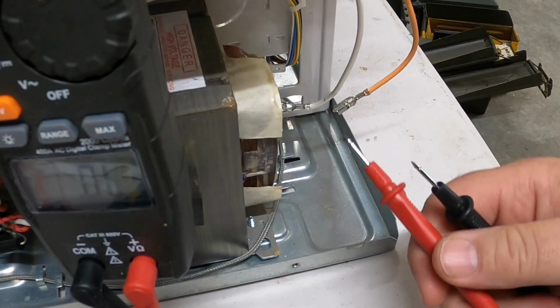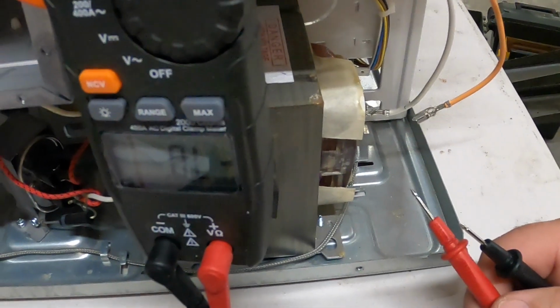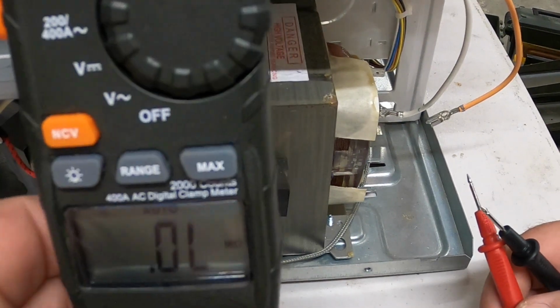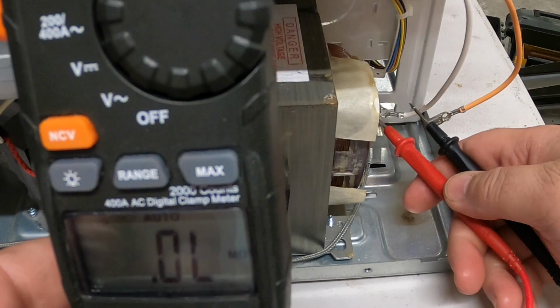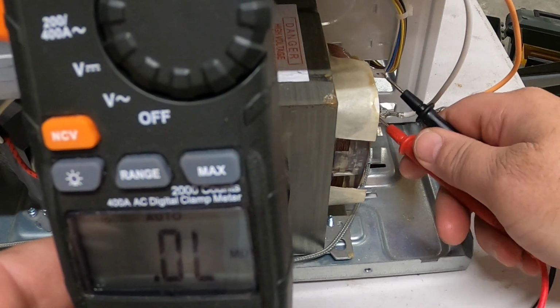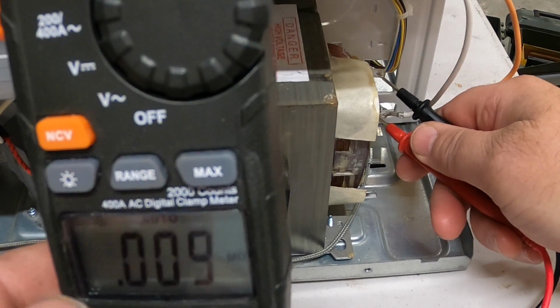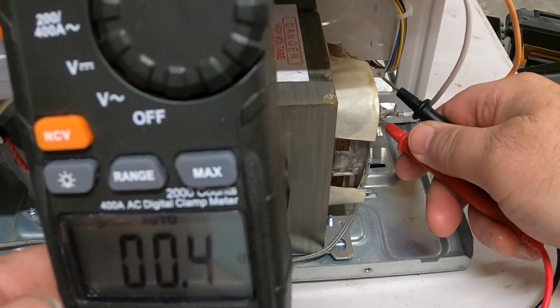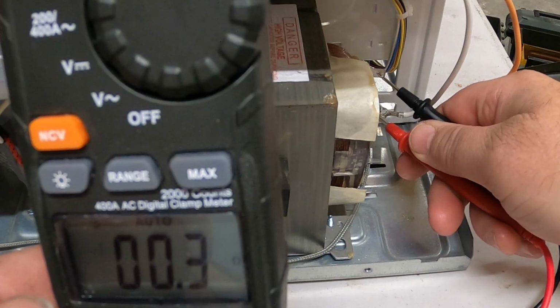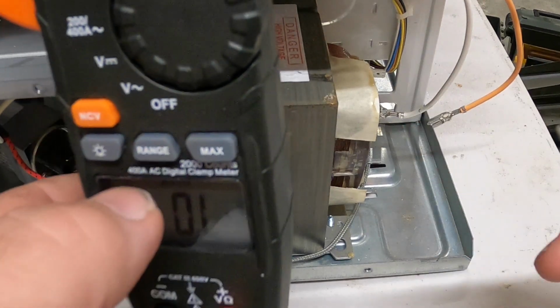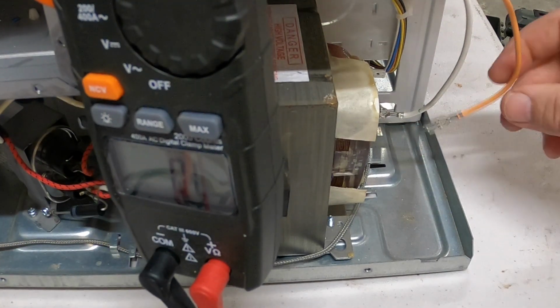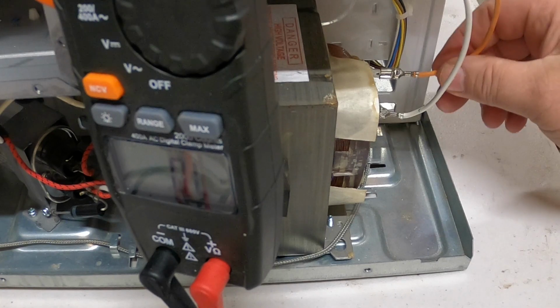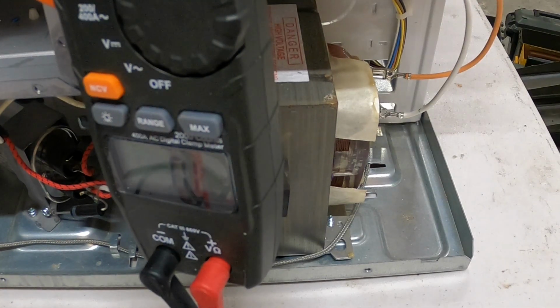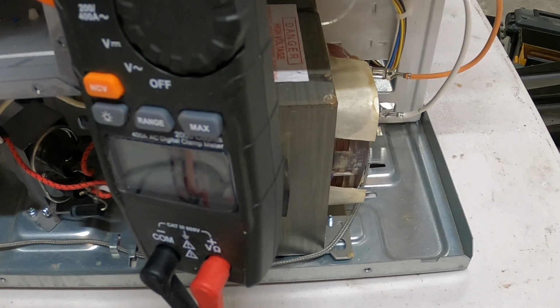You come in here, try to get the meter in. Okay, you notice how it reads 0.3, 0.4 ohms. You shouldn't have zero, but you should have very, very close to 0 ohms on the primary coil of your transformer. Every so often you'll get an open transformer.